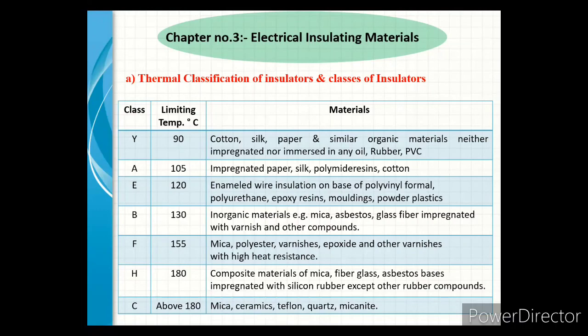Class H has a limiting temperature range of 180°C. Materials included are composite materials of mica, fiberglass, and asbestos base impregnated with silicone rubber, excluding other rubber compounds. Class C also has a limiting temperature range above 180°C. Materials included are mica, ceramics, teflon, quartz, and mica products.